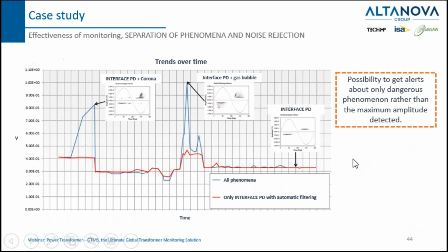In this graph, I think a very important one, you can see the trend over time of basically 4 weeks of the partial discharge activity. You can see two different lines. The blue line is related to all phenomena plotted together. By all phenomena, I mean the interface PD, the bubble PD, and some other corona effects acquired by the system. And the red one is related only to the most dangerous phenomenon, which in this case is the interface PD.